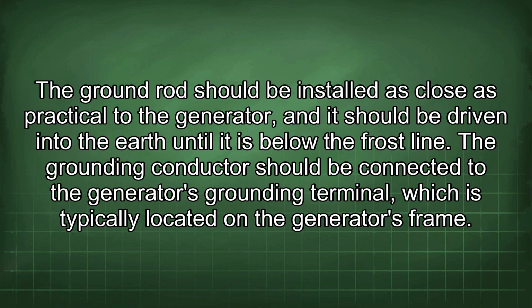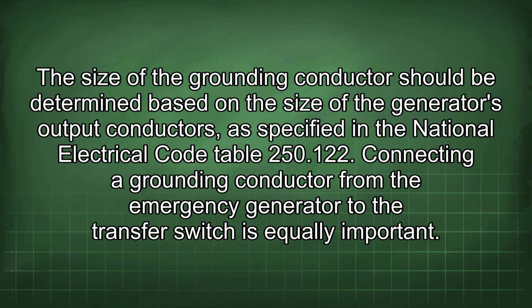The ground rod should be installed as close as practical to the generator, and it should be driven into the earth until it is below the frost line. The grounding conductor should be connected to the generator's grounding terminal, which is typically located on the generator's frame. The size of the grounding conductor should be determined based on the size of the generator's output conductors, as specified in the National Electrical Code Table 250.122.